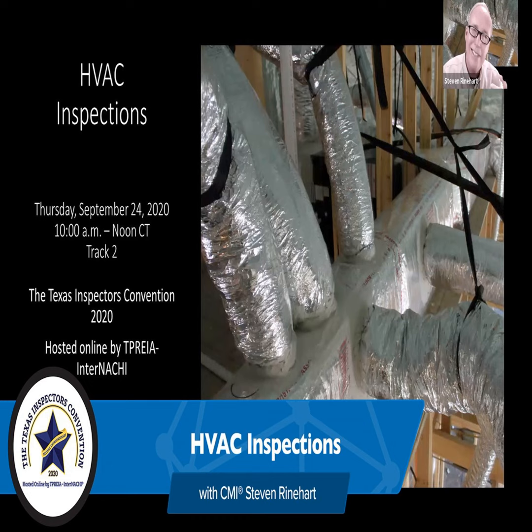Units and thermostats, I guess it's talking about all the components, how you do the structure here. When it's in the garage, it's got to be at least 18 inches. If you were in the earlier pre-cover class, I may have said, if it's in a garage, on a platform, I'd like to see it at least 30 inches off the floor for practical purposes. I want, on the other side in the house, to be able to put an adequately sized return.